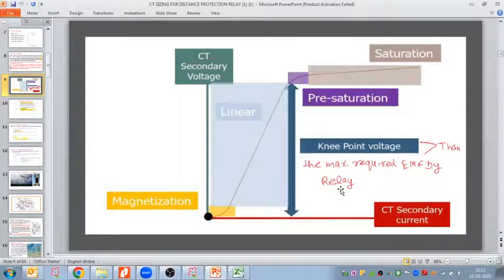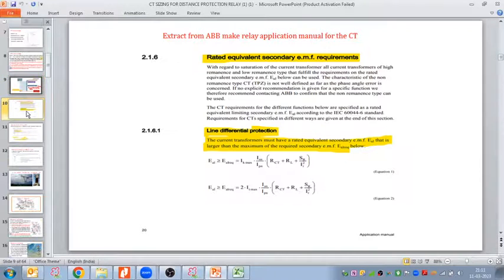So for that we will go to the relay applications manual, and from that manual we will take what CT requirement is given, and based on that CT requirement we calculate what the CT knee point voltage should be. This we have all seen in a study class. Just quickly refresh. So this is the CT knee point voltage calculation.